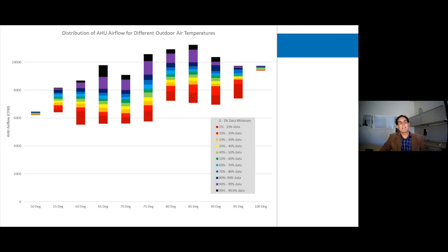So that black color at the top of the rainbow represents the top 1% of points within that temperature bin. And then the purple bar is the top 10% of data for that temperature bin. The green bands in the middle go between 40 and 60% within that temperature bin.